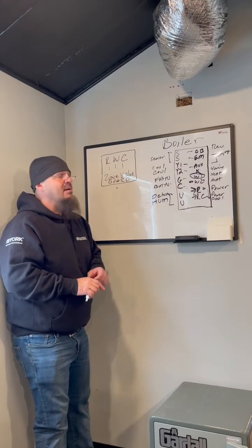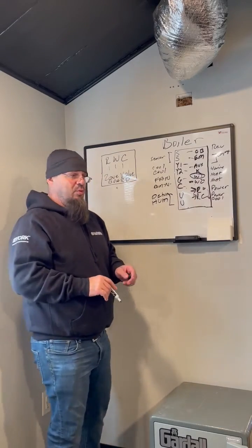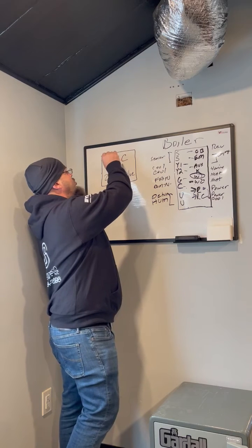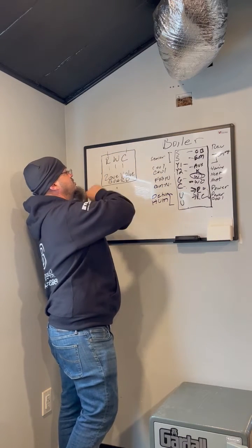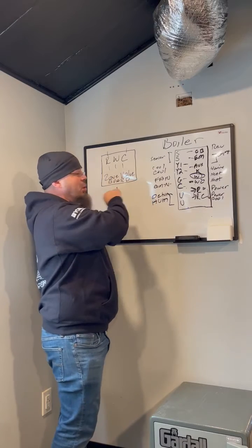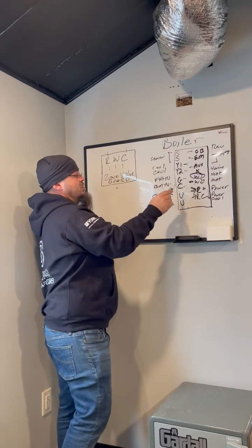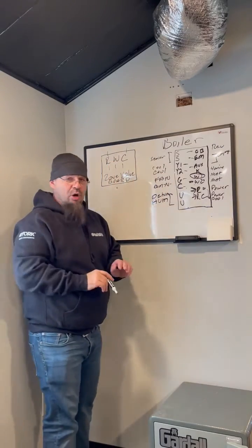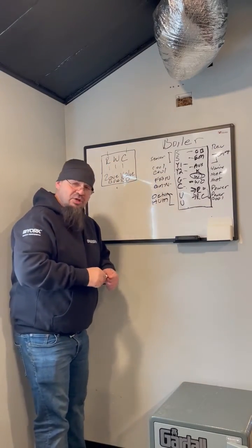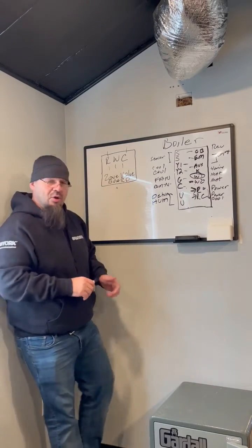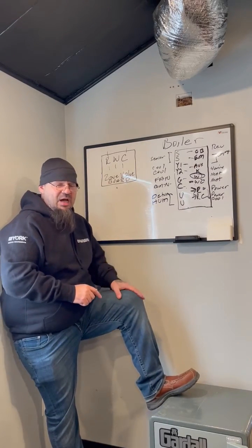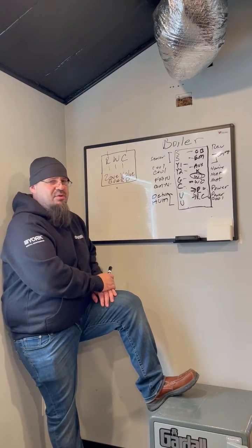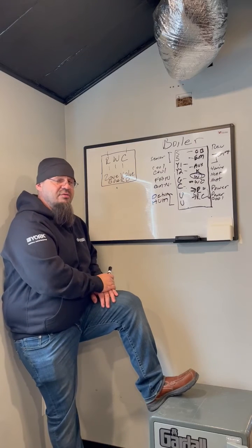If you have that, then you can, in a relatively simple way, hook up that power stealing thermostat by using your R and your C terminals right from the zone valve board to R and C on here, and then hook your white up to white, and it will actually work perfectly fine. We have Taco zone valve boards with power stealing thermostats all over the place. They do a fabulous job, and they will work readily, and often have 3 wire to them. Some of the times have 3 wire already run to the thermostat.